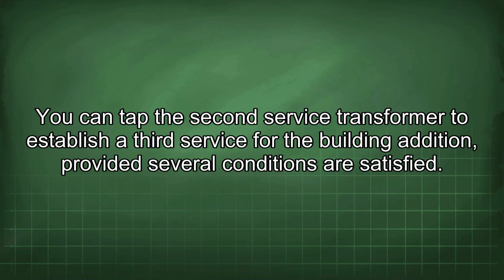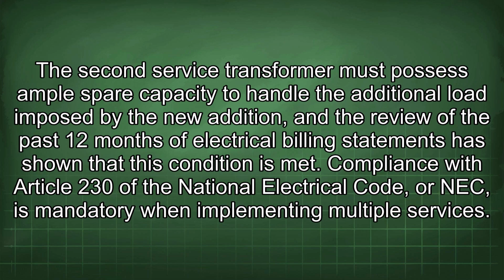You can tap the second service transformer to establish a third service for the building addition, provided several conditions are satisfied. The second service transformer must possess ample spare capacity to handle the additional load imposed by the new addition, and the review of the past 12 months of electrical billing statements has shown that this condition is met.